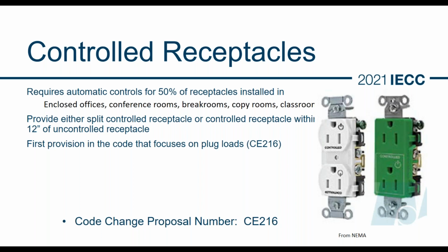For the receptacles you have two options. One is that you can switch the top of the receptacle on a control, while the bottom of the receptacle remains hot the whole time. Or you can install a receptacle that's completely switched and another receptacle next to it, within 12 inches, that is not switched. So it gives you the option of which receptacles to use for plugging in your desk equipment and that type of thing. This proposal did pass by committee.